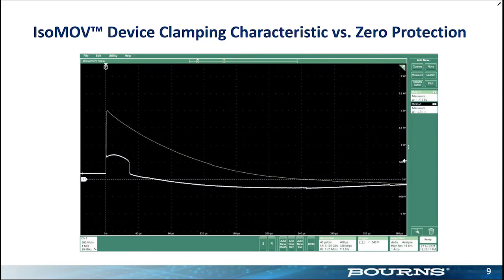So I need to remind you that that spike is very narrow. For example, your equipment is assuredly protected against ESD, right? That's 8 kV, but it's very, very short. There's not much energy in there. Well, this is 1.5 kV, and it's probably a few 100 nanoseconds wide. There's really not much energy in that pulse. There's a lot more energy in that lower, longer pulse.